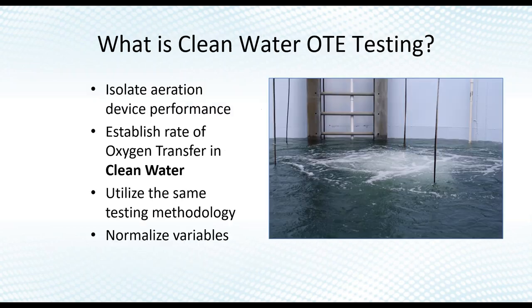We evaluate oxygen transfer with a process called clean water OTE testing, or clean water oxygen transfer testing. The idea is to isolate the aerator's performance. A wastewater facility has all sorts of variables — dirty water, surfactants, uneven bottoms, multiple aerators. How do you isolate the performance of one aerator? That's the purpose of OTE testing: to take one device and test it for its maximum performance in clean water.